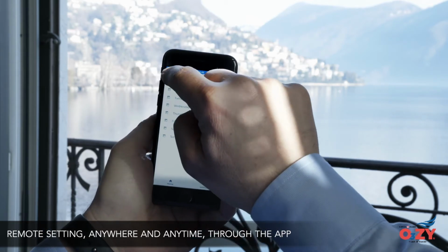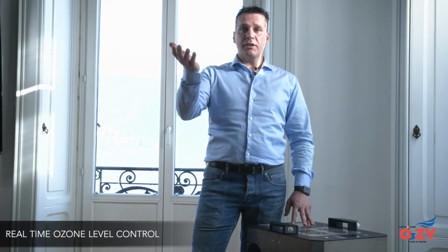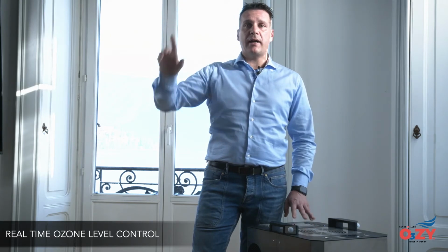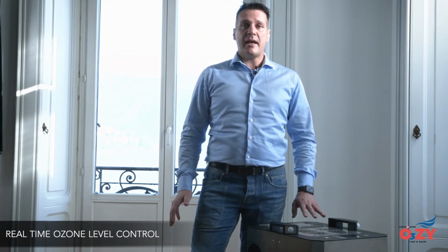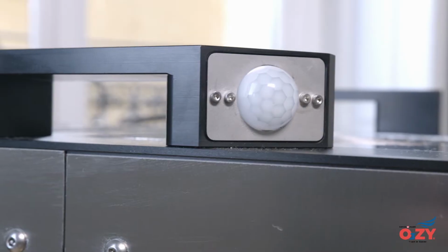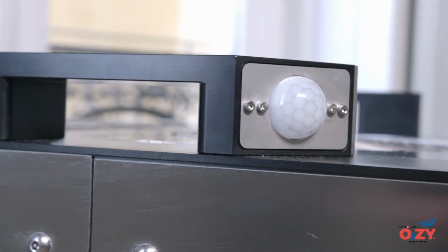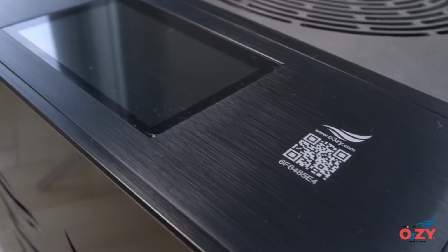How do I know that the ozone level is enough to sanitize the environment? O3ZY uses an electrochemical ozone sensor, validated by a third-party certification entity. These certified sensors can measure, control, and manage ozone. This way, it is possible to monitor two details in real time: the physical ozone value in the air and the chart related to the current sanitation cycle. These elements combine to perform a controlled sanitation cycle and to be immediately updated through the O3ZY app.